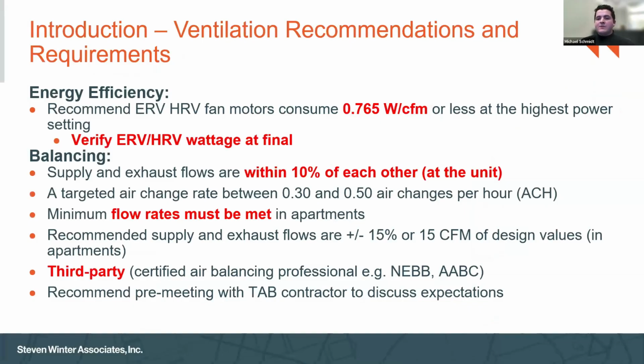So let's talk for a moment, again framing the conversation, about some of the recommendations and requirements for passive house and how they might affect the design. Starting from the top, as far as energy efficiency, typically it's recommended that fan motors in ERVs or HRVs consume about 0.765 watts per CFM. This is a recommendation, not a stern requirement, but typically we're seeing oversized units using a larger fan spinning a little bit slower to reach this watts per CFM target. Verifying the final wattage is not a strict requirement, but is an internal standard that we have set here at Steven Winter Associates in conjunction with our commissioning team.